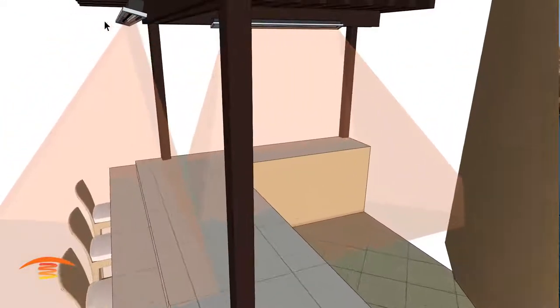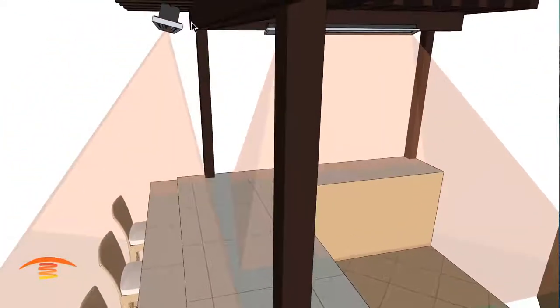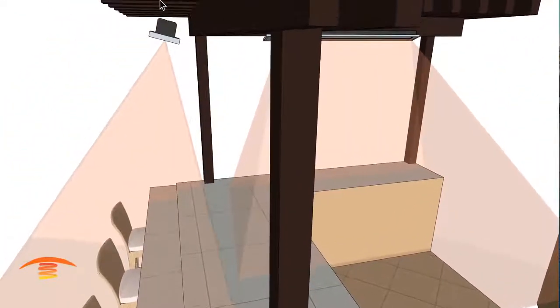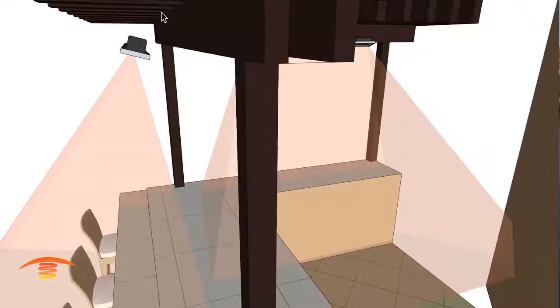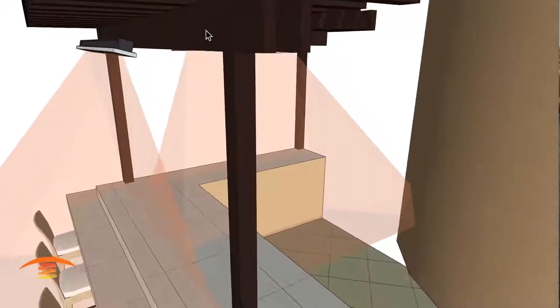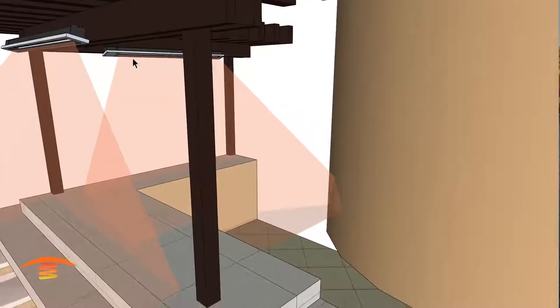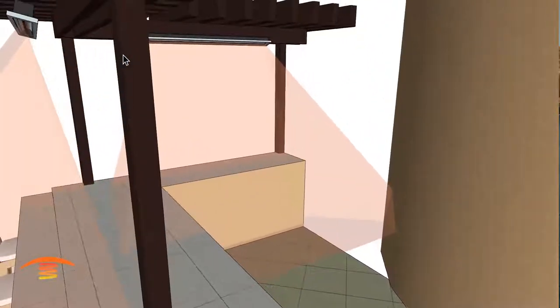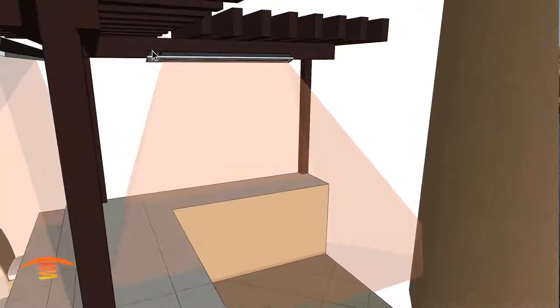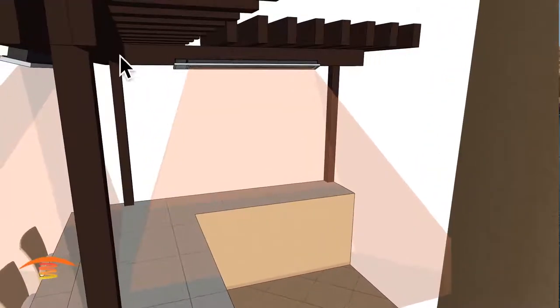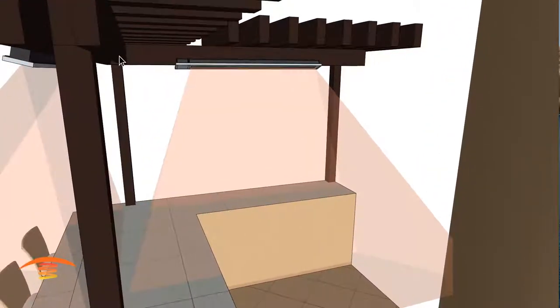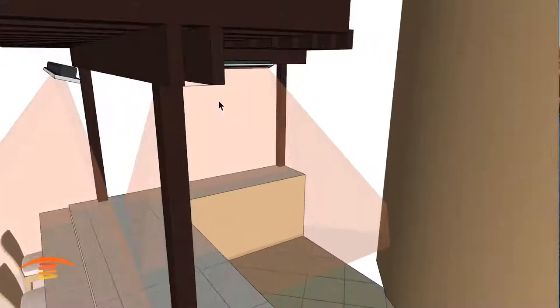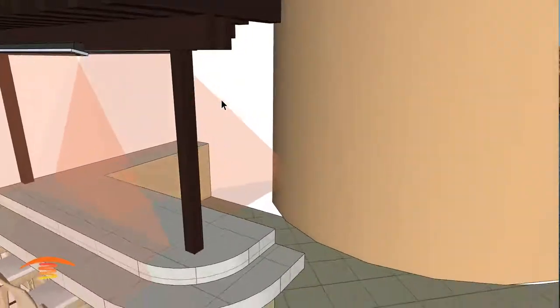That's not necessary, but it's the same clearances as this. The clearance here, six inches there, six inches above, same over there. This one over here is 18 inches from this edge, so we're not heating up that wood in any way.